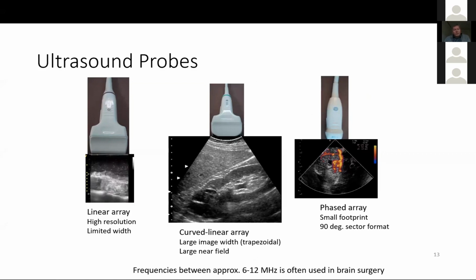And then you have the curved linear array as another category. You have a trapezoidal shape of the ultrasound image, so you can have a larger field of view in the deeper parts, so you can have a better overview. You can also have a quite large near field, but it's limited by the size of the array.